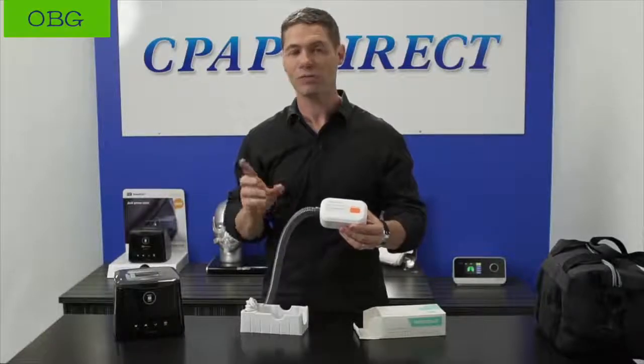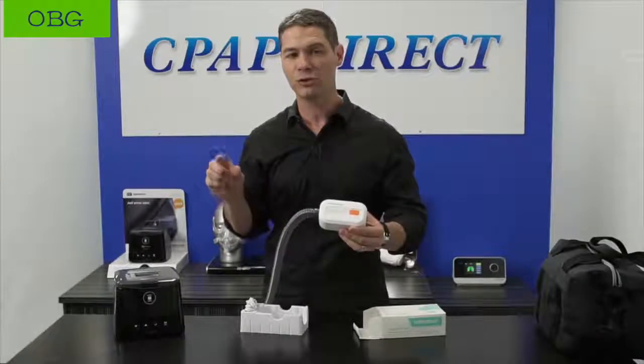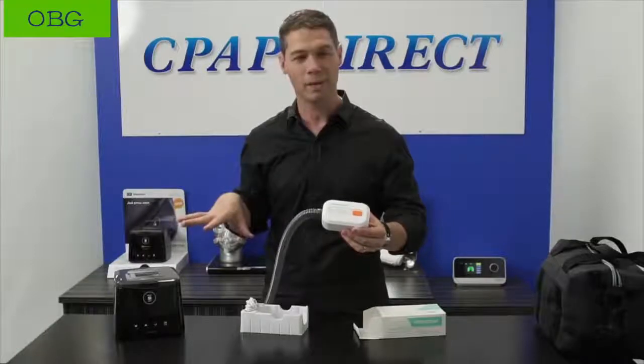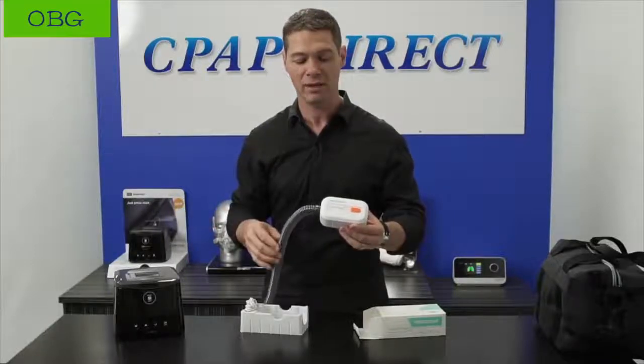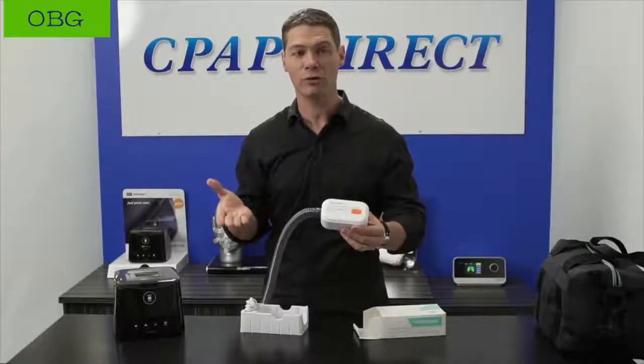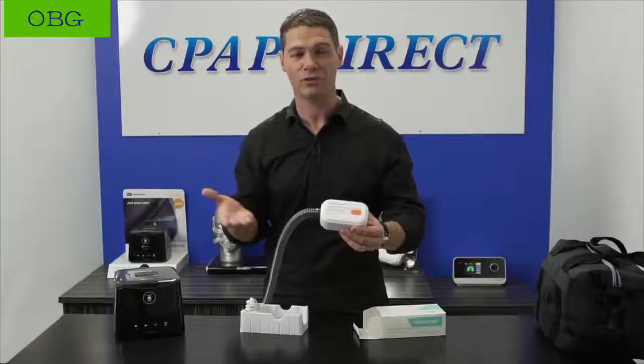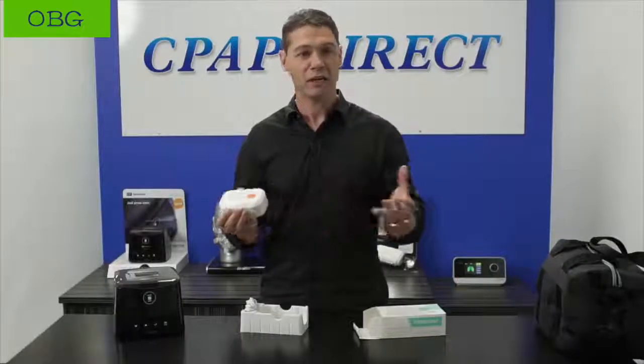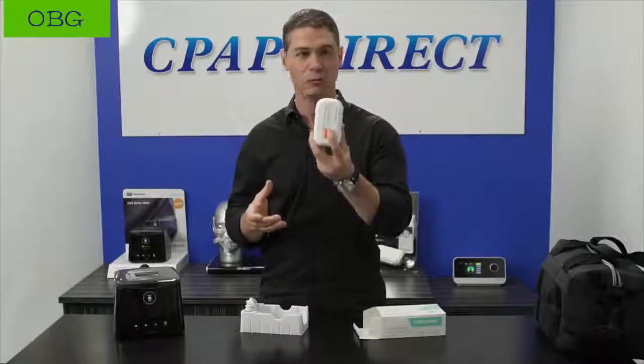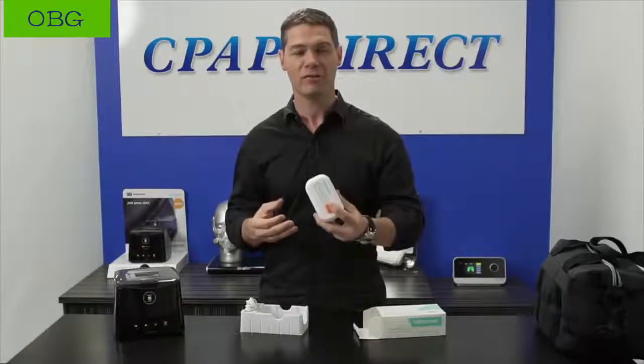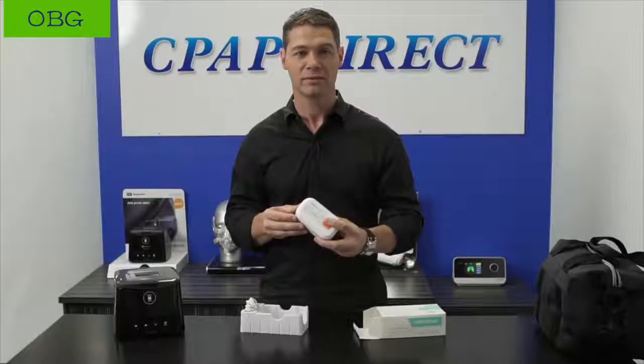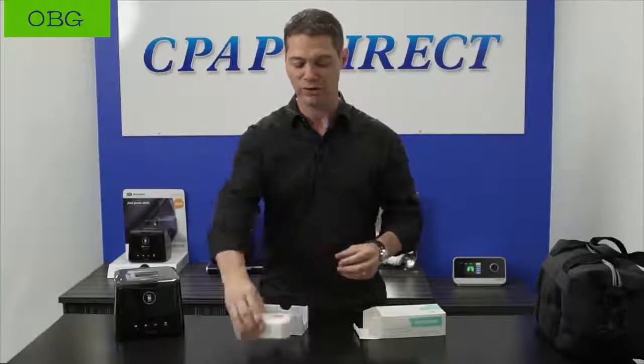It's really important from a safety perspective not to use your device or any of your Cpap gear for at least an hour after the cycle is finished, just to give the ozone or the activated oxygen time to dissipate. If you want to disinfect your mask as well, after you've washed it and cleaned all of the oils off it, simply put it in a plastic container like a Tupperware container, and again, run the cycle. Leave it there for 35 minutes, and of course wait an hour afterwards before you use the device.